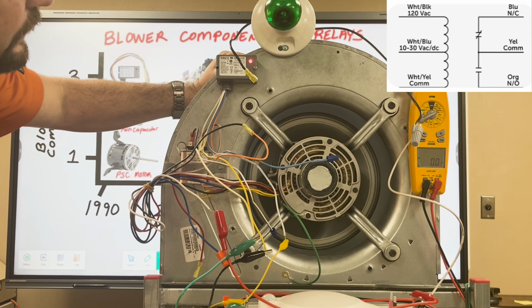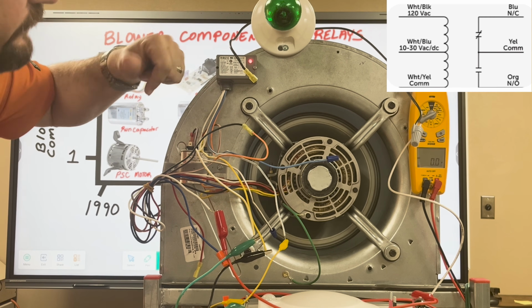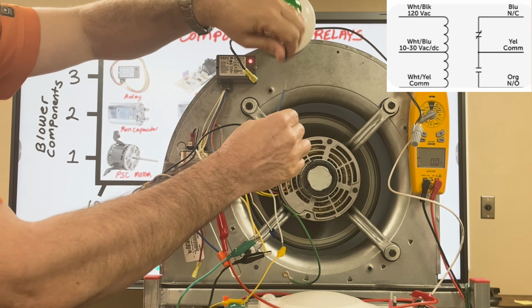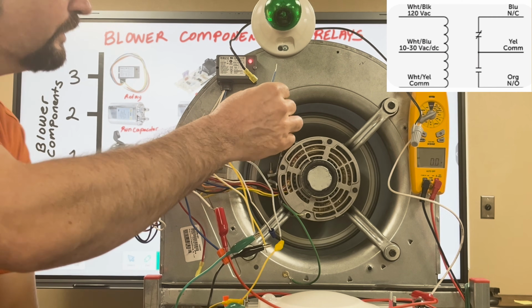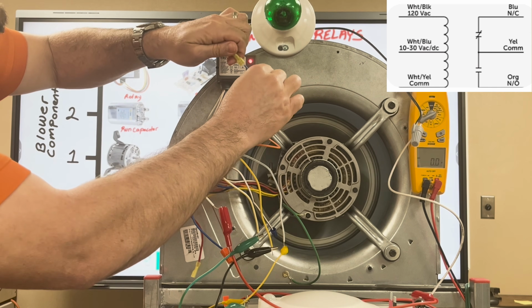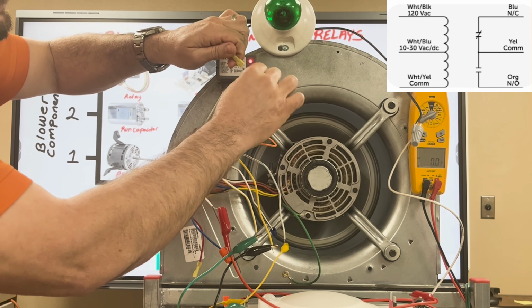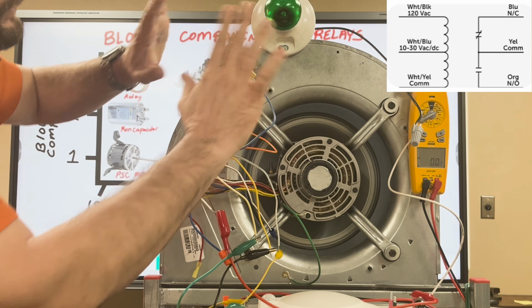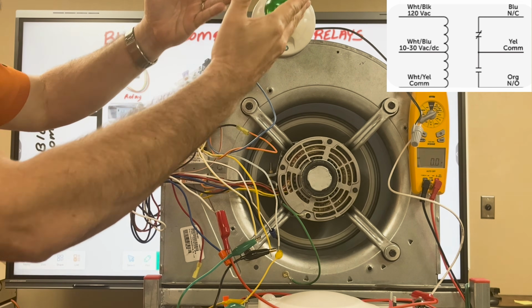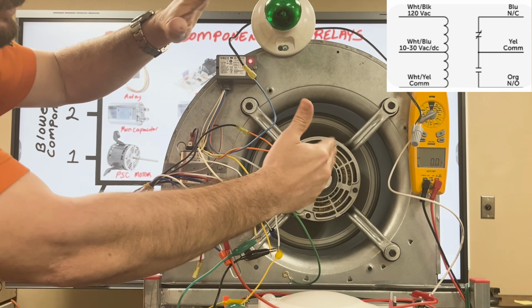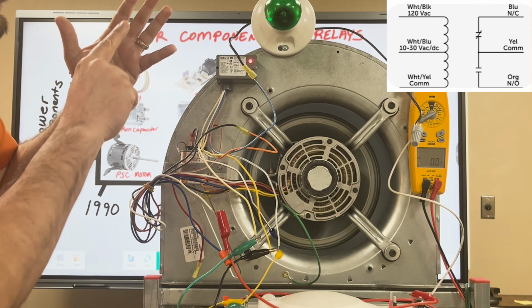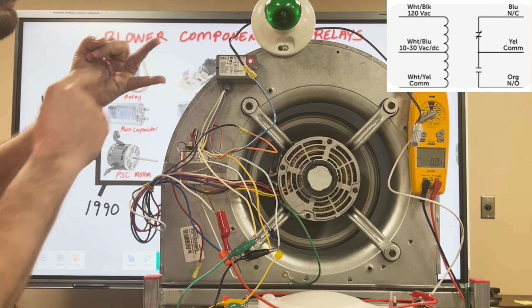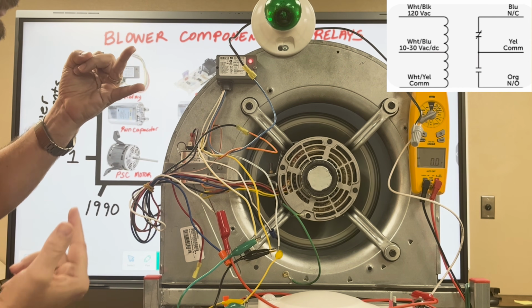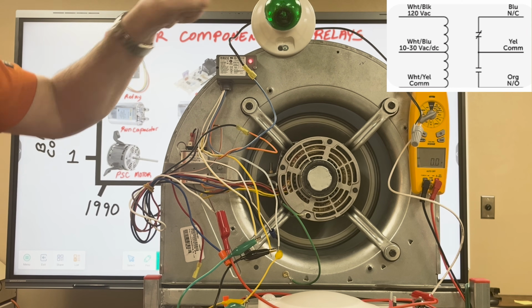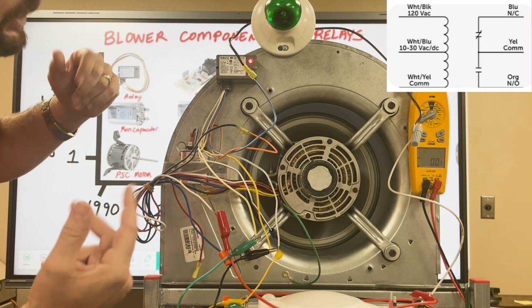And so if I wanted to wire one of these normally closed ones to my light, I have blue here. I can simply take this, come out of that, go ahead and, excuse me, there we go. That should stick. And now if I lose 24 volts, my light will come on. This is wired up 2 loads to my relay using the normally closed and the normally open, orange and blue. And if I were to remove 24 volts, then the top load will come on and the bottom load, the motor, will shut off.